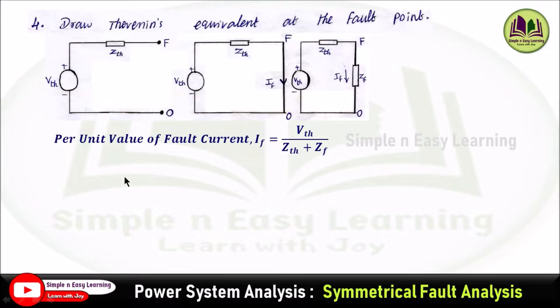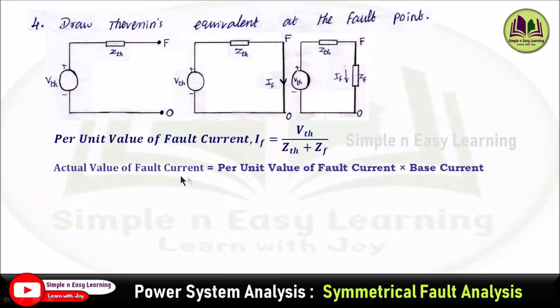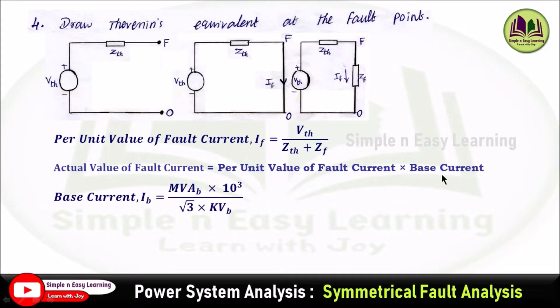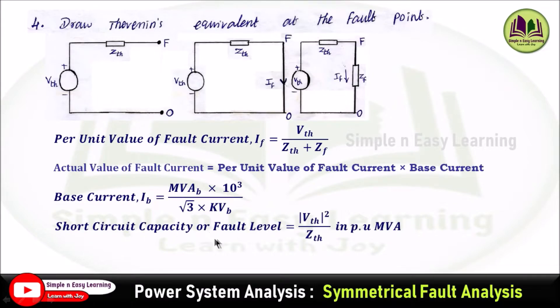We need to calculate the fault current. The per unit value of fault current I_F will be equal to V_Thevenin divided by Z_Thevenin plus fault impedance Z_F. The actual value of fault current equals the per unit value multiplied by the base current. The base current expression is: MVAB × 10³ divided by root 3 times KVB, where MVAB and KVB are the base values. Short circuit capacity or fault level can be estimated as V_Thevenin squared divided by Z_Thevenin in per unit MVA.